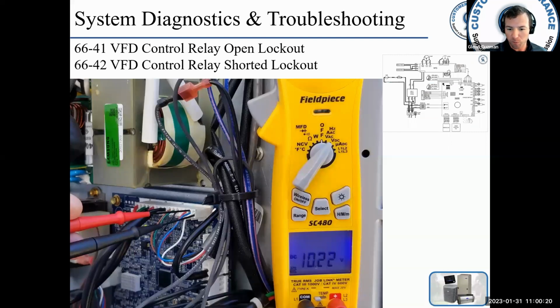So again, between the blue and white, checking it here on the PCM, you can see me checking it there. Now it says 12 volts DC. This was a properly operating unit, 10.2. Okay, there was nothing wrong with the unit. Okay, so you may have a little bit of variance, I should say, with your meter. Okay, so keep that in mind.